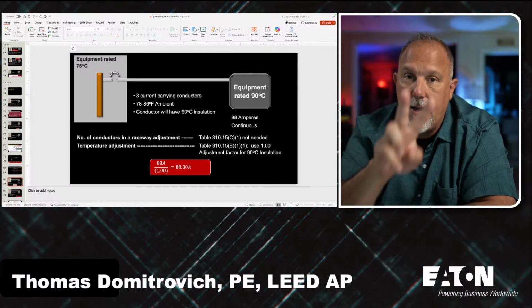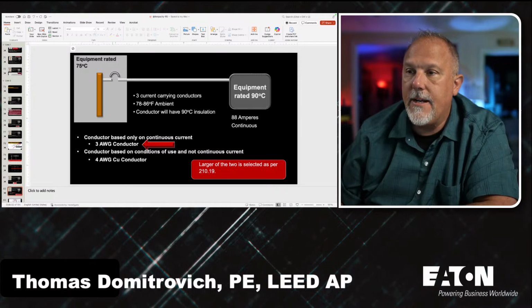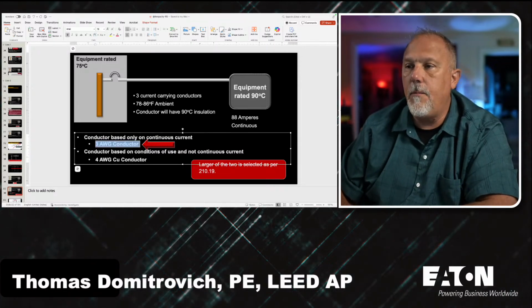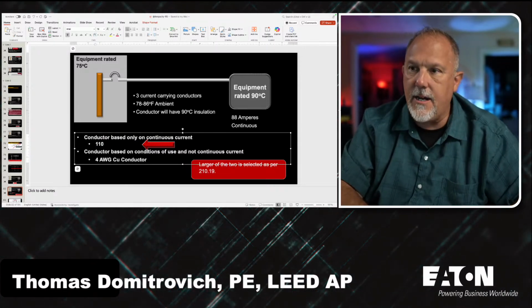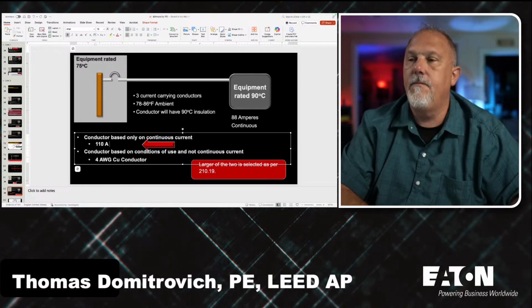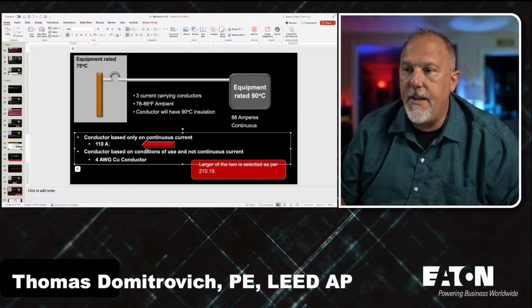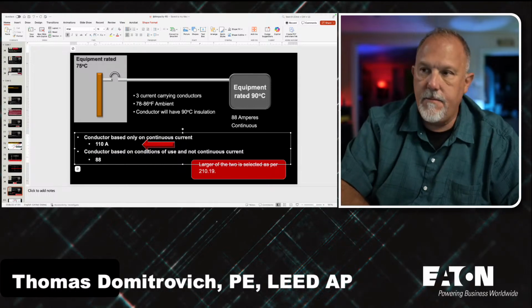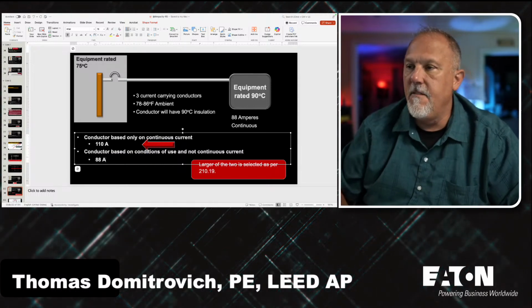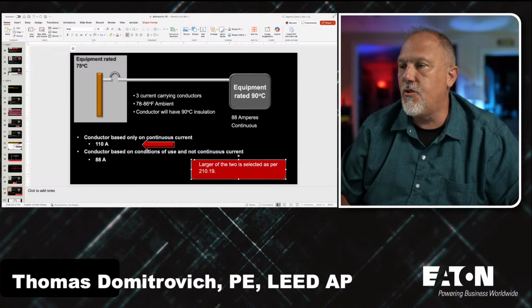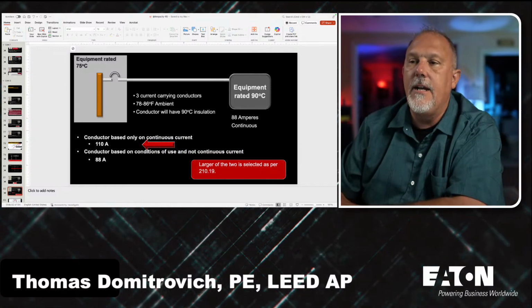So I've got my two values, right? And I have to change this. My conductor, based only on that, is 110 amps. And this was 88 amps. Okay. The larger of the two has to be selected.